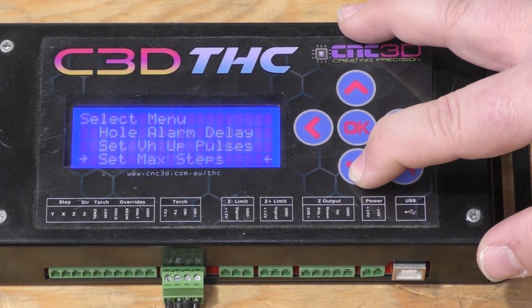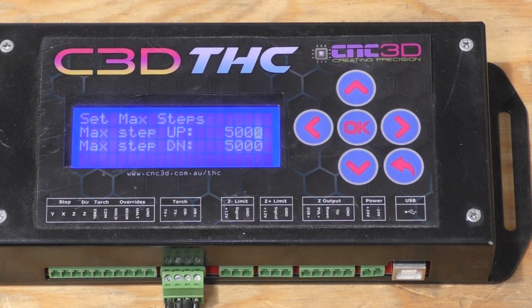Next menu down will be set max steps. So this is how many pulses the motor will move up or down from the start, so the position it is when it starts. So this is a safety feature. So if you're, let's say, you got over the edge of the stock, but you're pretty close to the maximum travel on your Z-axis, you can set this value so that the Z-axis will not crash into itself. There are limit switch options on these machines, on these controllers as well. If you do not have the limit switches, this is your safer option. So this will only allow the THC to command the Z-axis to move up or down. In my case here, 5,000 pulses.